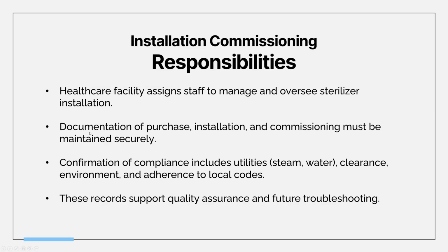Hospitals must assign qualified staff to oversee the installation. They have to maintain purchase and installation records and confirm all local codes and CSA standards are met. They also have to record utility readings, test results, and the installation plans. Proper documentation is crucial for troubleshooting, maintenance, and any future audits.